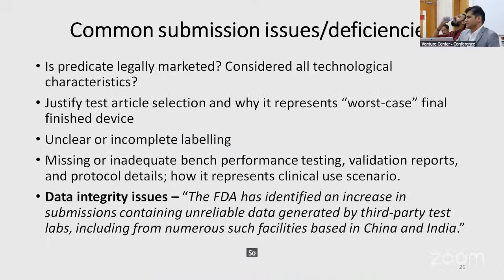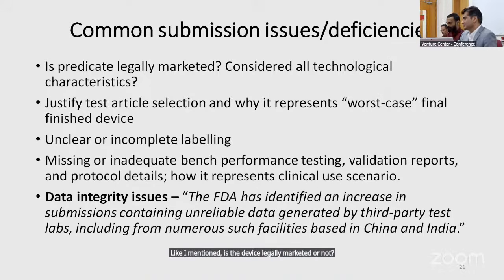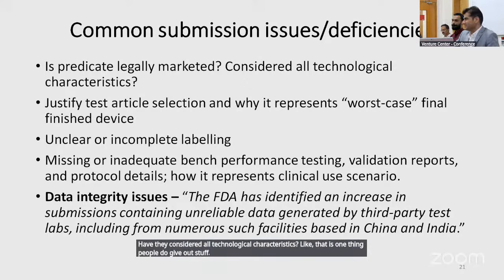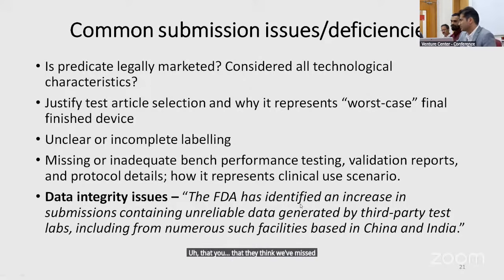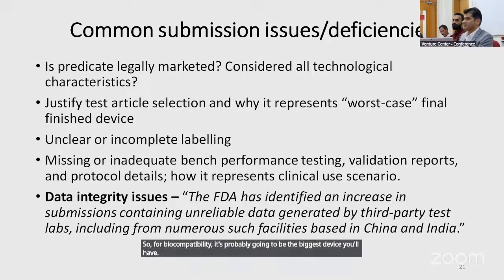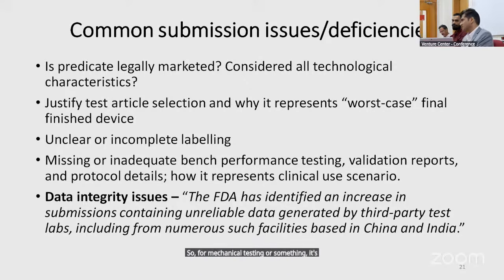Right, so last one, common issues. Like I mentioned, is the device legally marketed or not? Have they considered all technological characteristics? Like that is one way people do leave out stuff that they think we've missed, but can't see the device. Then the test article selection, this is a big one. Generally, what we're asking for is it should be a worst case representative for that particular test. So for biocompatibility, it's probably going to be the biggest device you have. But for mechanical testing or something, it's probably going to be the smallest device you have.